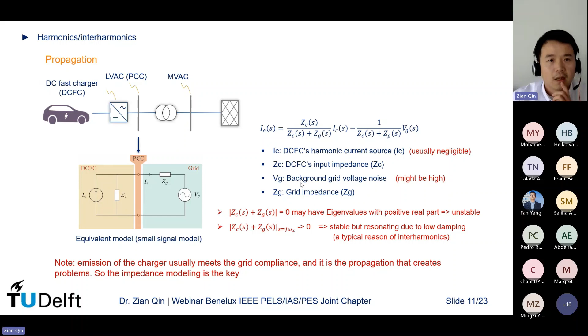Then, if there is such a problem, how can we solve it? Or when we design the EV charger, how can we evaluate beforehand whether there is going to be this problem or not? So we need to model the impedance, right? To model the impedance of the charger, you basically have a few options. The very widely used one is the so-called black box measurement. You connect the charger to a grid emulator and use the grid emulator to inject a voltage perturbation into the charger. As a response, the charger will give you a current perturbation, and the ratio between the voltage and current perturbation is going to be the impedance. Then you do a frequency sweep, and you get a broadband impedance of the charger.